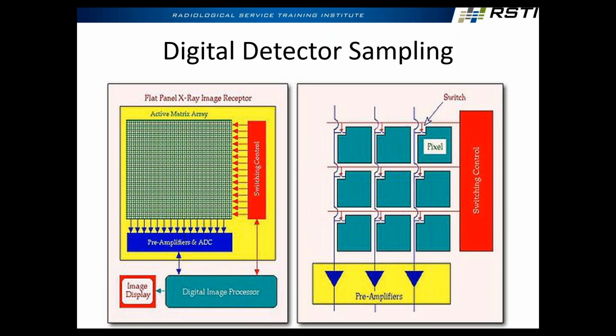What's happening now? Processing speed, processing time, the amount of data I have to transfer and store, all those things become exponential. Think about 1 square, and you double your resolution, you've quadrupled your storage requirements, right? If you take this pixel and now you double your resolution, you have 4 times the data you have to deal with and process and store and transmit. In fact, nowadays the limiting factor for imaging is not the detector technology at all. It's the processing and the computer power to keep up with the images at that resolution.